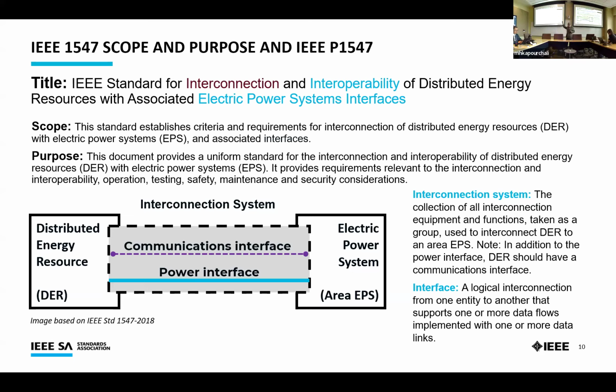Right before this was published, Hurricane Sandy hit, and all these PV panels in New Jersey and along the eastern seaboard - people were frustrated and complained to local governments that they couldn't get their solar panels to work, and their utility couldn't tell them why. It's because they were compliant with IEEE 1547, whose baseline requirement is that if the local grid is out, you can't backfeed that grid unless you're isolated. So there was no way to make all these standard-compliant devices carry load. You need a certain amount of infrastructure in place to isolate yourself.